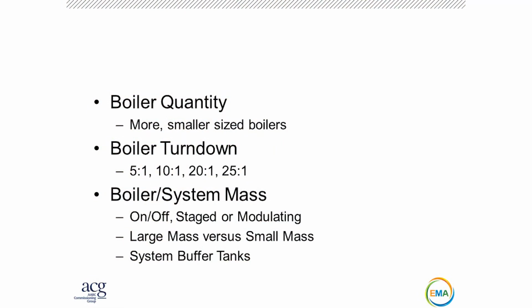So solving the boiler cycling problem, you can do it a bunch of different ways. You could go non-condensing, but a bunch of boilers. Instead of one big 10 million BTU boiler that's on-off, if you had 10 1 million BTU boilers, I have the same total BTUs, but it's broken up. And now I can run one or two if the load is small. And they'll actually run and continue running because the load is small. They're matching the load. So I could stay non-condensing, but help solve the cycling problem with multiple boilers instead of one big one.